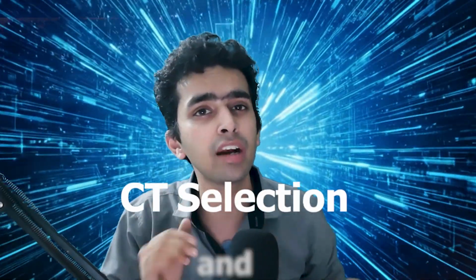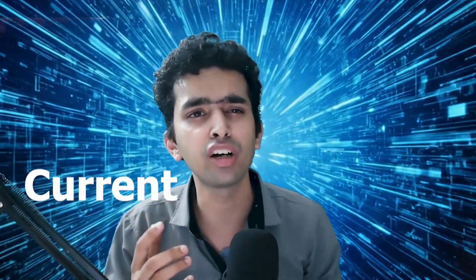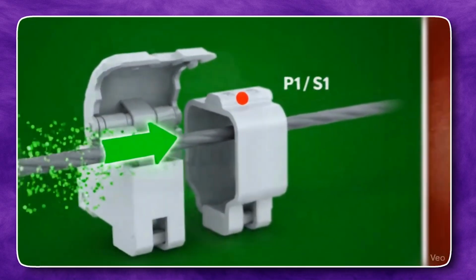Now, before ending, let's get into the practical buying and installation tips for dual source energy meters. These aren't theory tips, these are what your field team or electrician will definitely ask before commissioning. First one is the CT selection and rating. First, we choose the right CTs. CT stands for current transformers, whether 100/5 ampere, 200/5 ampere, or higher. And always check the CT polarity and direction during installation. If these are reversed or disconnected, your meter readings will be completely off.